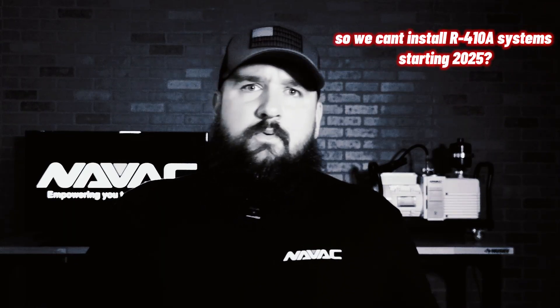We can't install R410A systems starting in 2025 — that is not what I am saying at all. Currently, for installation of existing R410A equipment — equipment that has already been brought to the states and is currently sitting in your distributors and supply houses across the country — you are still allowed to install R410A equipment all the way up until 2026. Any R410A equipment that is currently here is able to be used, installed, and sold up until 2026.